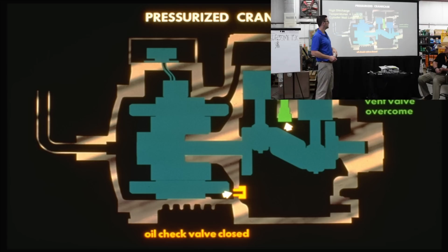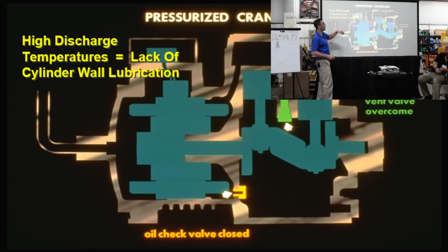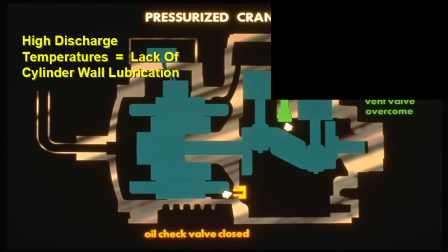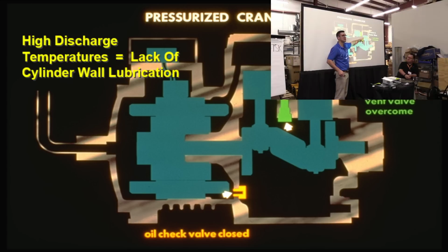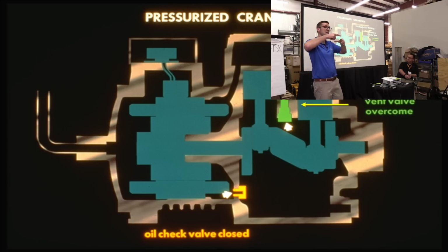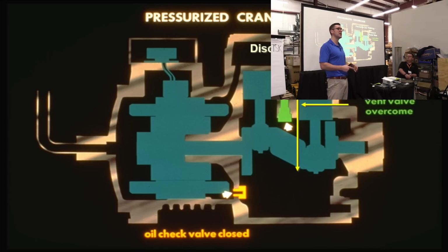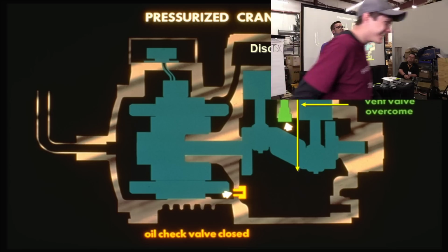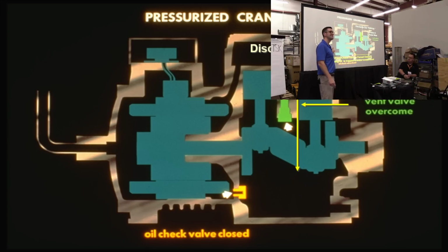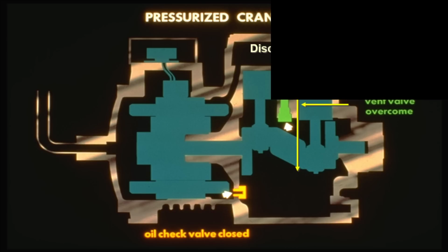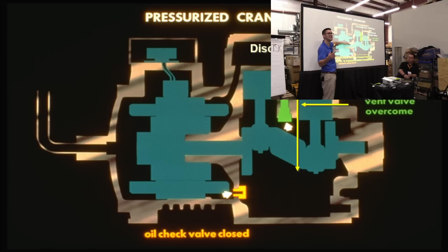Okay. High discharge temperature, lack of cylinder wall lubrication. So now that's running. Piston and cylinder wall wear. Okay, then what happens? We get what we call blow-by. That compressor's pushing up, but all that discharge gas is pushing down by it, right? What happens to this right here? Higher pressure. Higher pressure in here, so what does that do? It closes. So where's all my oil now? Stuck right here, right? So this is filling up. And then what happens? What did I show you earlier? You don't get any lubrication. No lubrication, but what trips off? Low oil pressure, right?